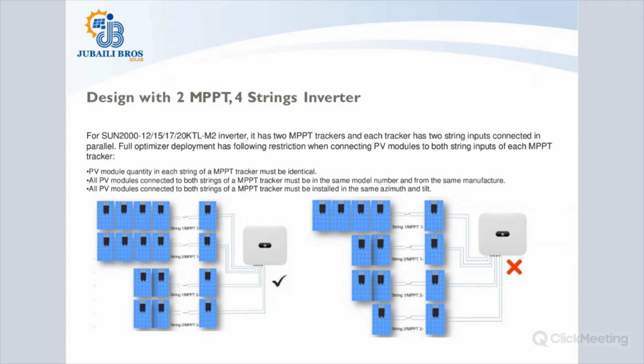Again, what's the Huawei recommendation? Now, if we come to the higher size inverters, in this case, I think I've jumped one more step. Okay, so in this case, we are considering the 12 to 20 kilowatt inverters, and here they have 2 MPPTs. Each MPPT has 2 strings. That makes it 4 strings in all. Remember, each MPPT is completely independent of the other MPPT, which means that you could actually install different sets of units to each MPPT. For example, MPPT 1 can have a different brand or make of PV modules. MPPT 2 can also have a different brand or make of PV modules. All you need to ensure is that the number is the same in each MPPT.